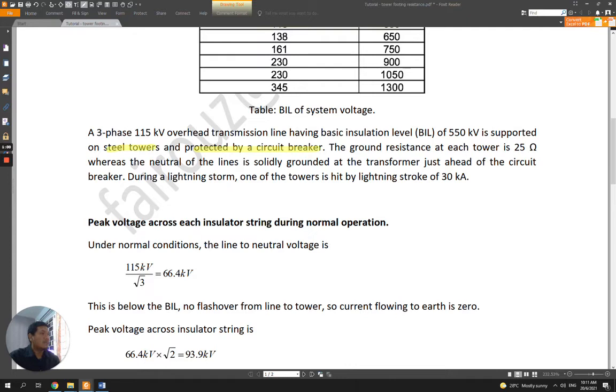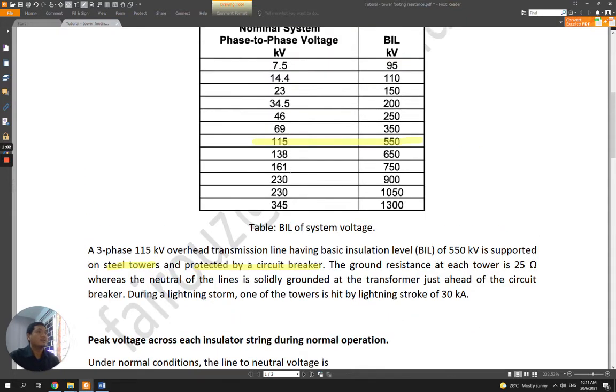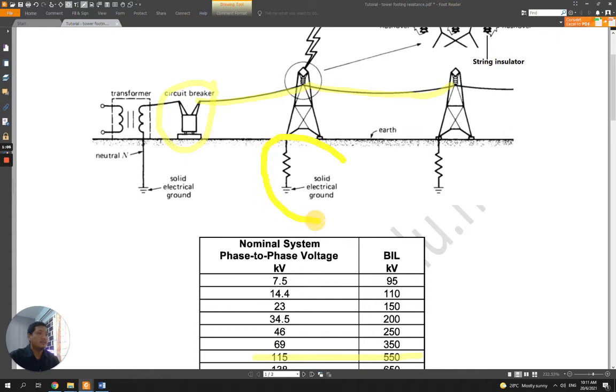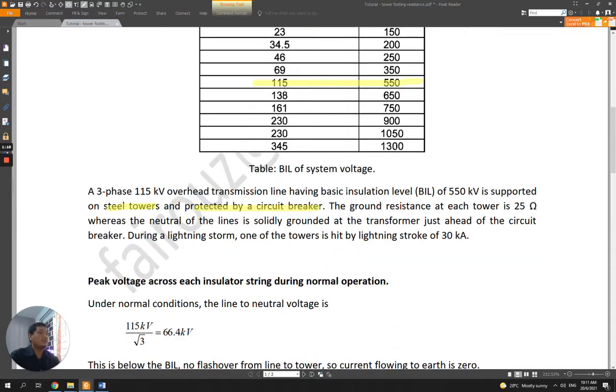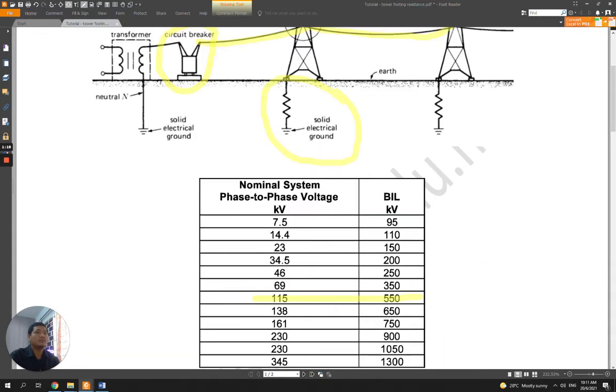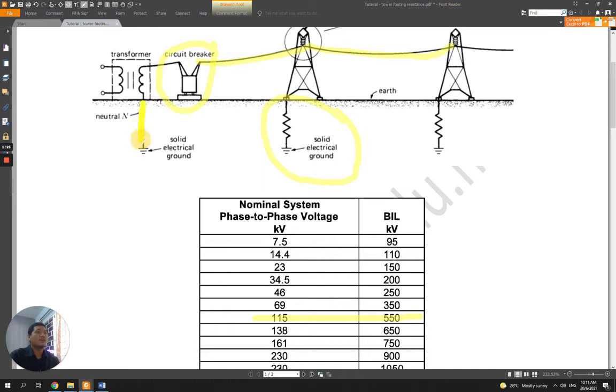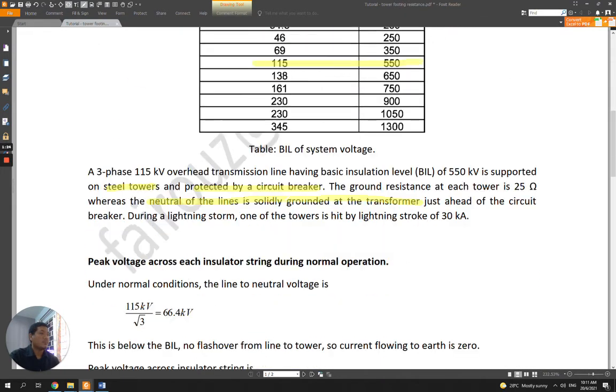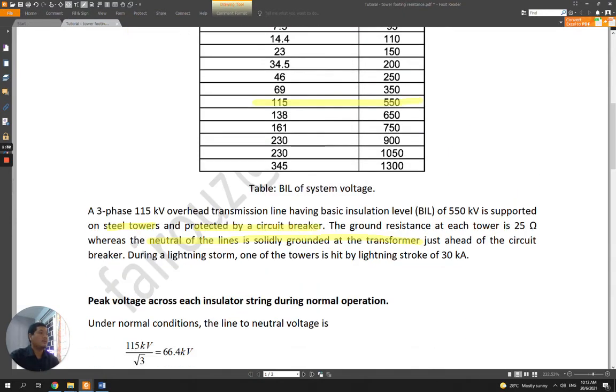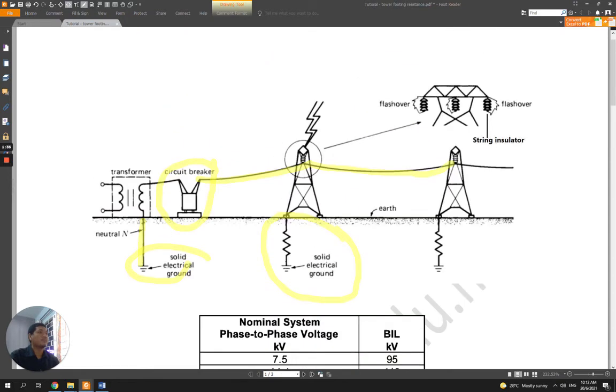So the ground resistance at each tower is 25 ohms. This is the tower footing resistance, measured to be 25 ohms, whereas the neutral of the line is solidly grounded at the transformer just ahead of the circuit breaker. You can see here the neutral is connected to the ground. So during a lightning storm, one of the towers is hit by a lightning stroke of 30 kiloamp. Okay, lightning stroke, 30 kiloamp, right?